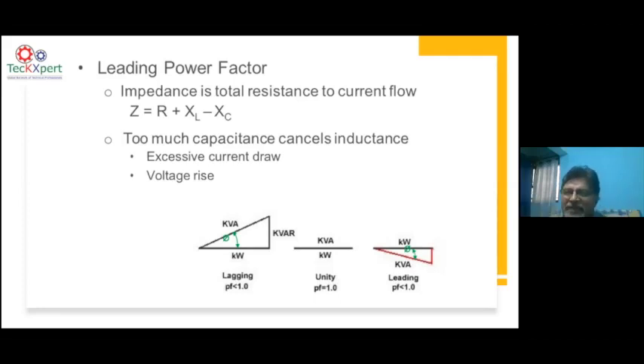That means a capacitor bank with an active harmonic filter can do this cycle-to-cycle correction of power factor on each 20 millisecond cycle on a real time basis. So that is the right solution to avoid the leading power factor problem. You can have an active harmonic filter with a capacitor bank together. Whenever you have a lagging power factor problem, you bring in more capacitors. Whenever you have a leading power factor problem, you bring in the active harmonic filter and inject lagging power factor so that it remains steady at unity power factor all the time. So that is one way of compensating this leading power factor problem.